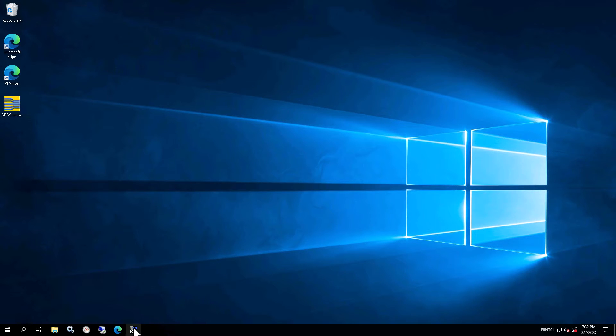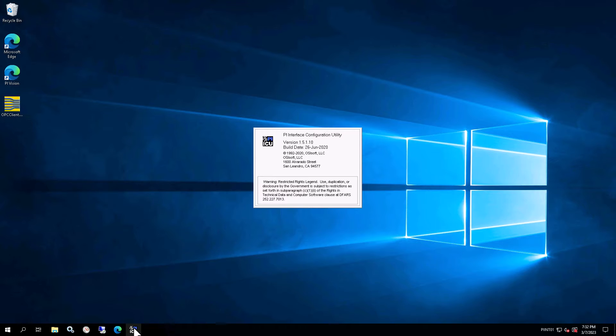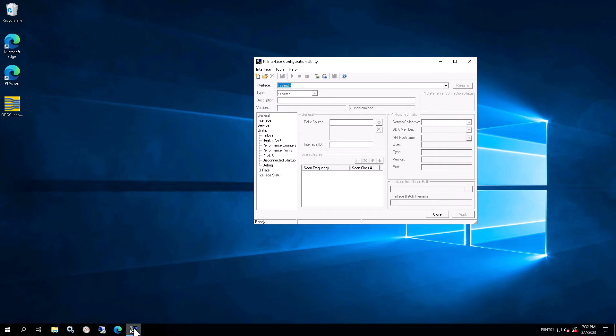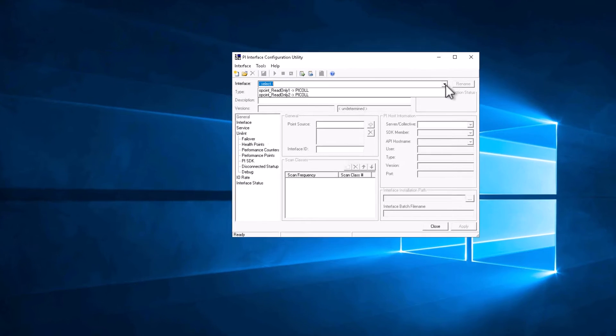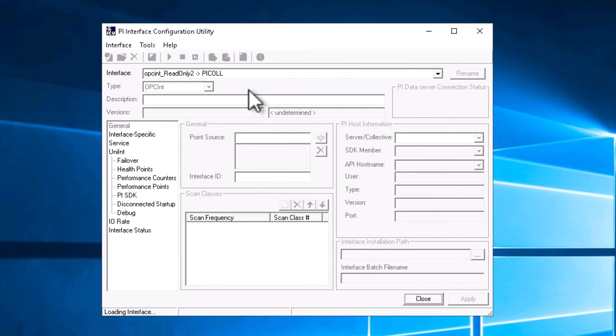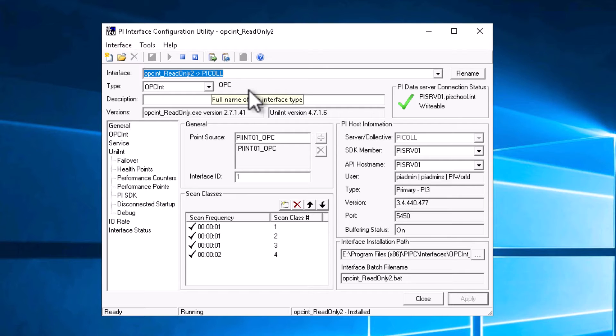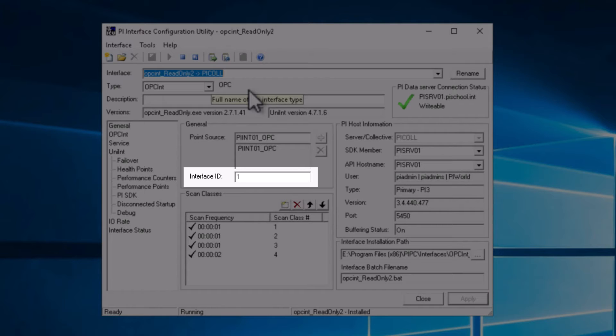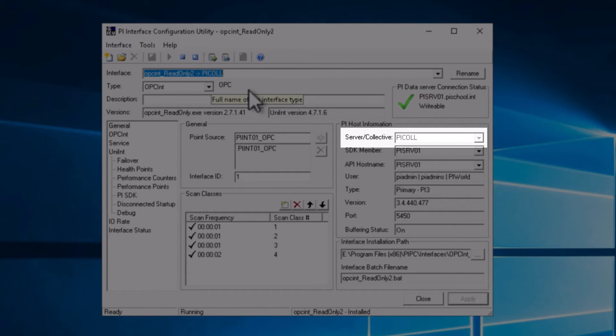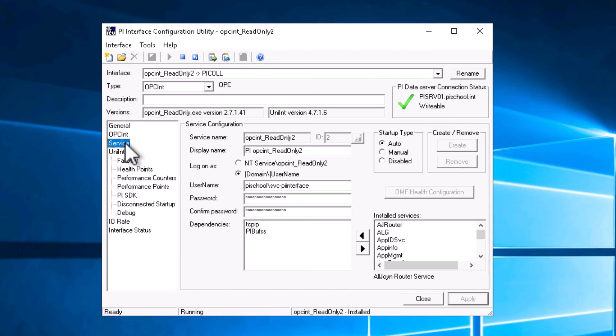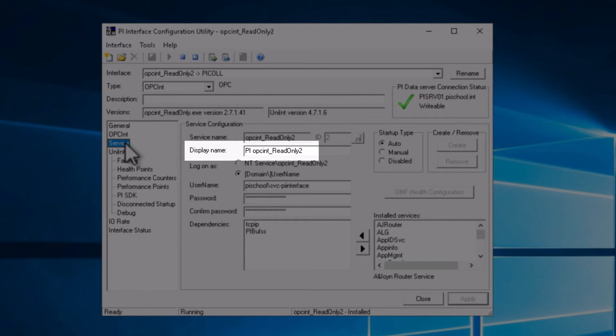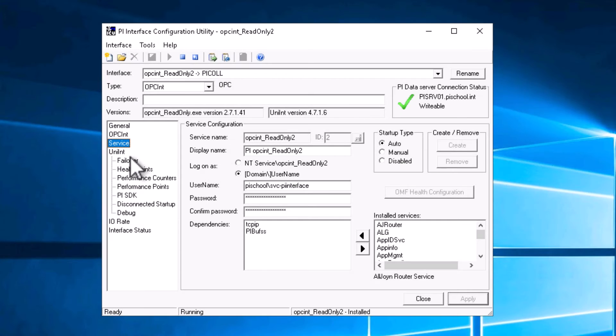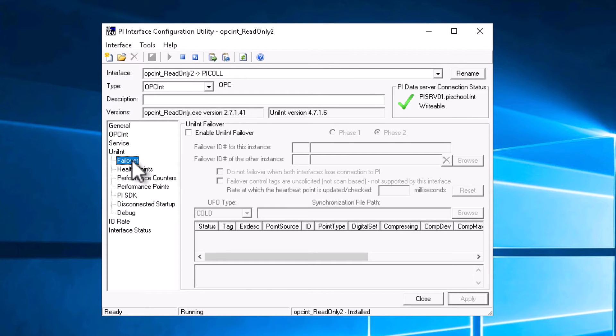In your web browser, connect to the PIIN01 server. On PIIN01, click on the ICU icon in the taskbar to open the Interface Configuration Utility. Select OPCINT Read Only 2, pointed at PI Server 01. On the General tab, note the point source — PIINT01 underscore OPC — the Interface ID: 1, and the Server Collective that it's writing to: PI-C-O-L-L. On the Service tab, note the Display Name: PI OPCINT underscore Read Only 2. On the Failover tab, note that Failover is not enabled.